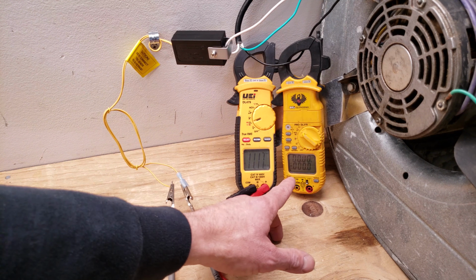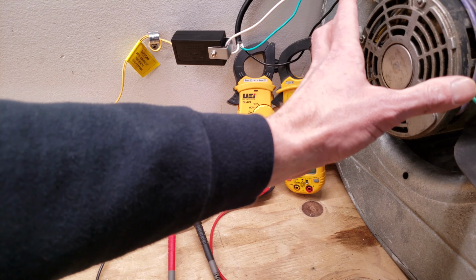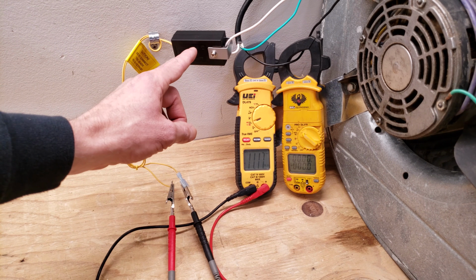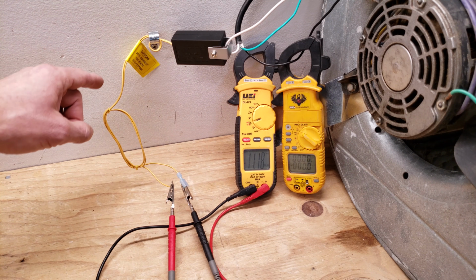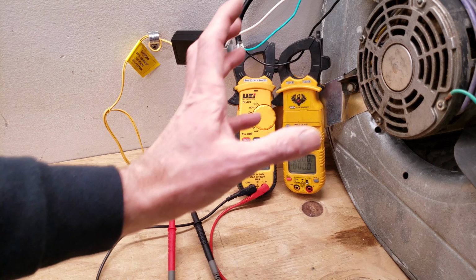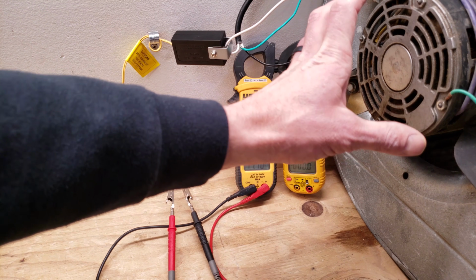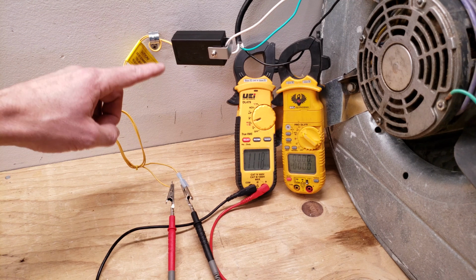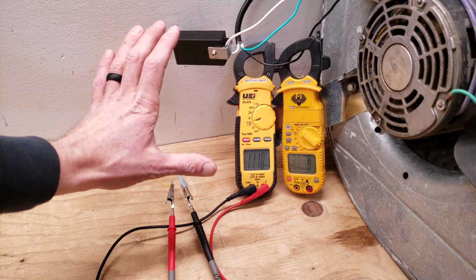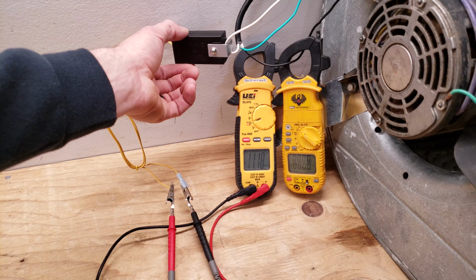But you need to make sure that you're drawing enough amperage on that blower motor for this current sensing relay to allow the 24 volts through. So on newer, higher efficiency blower motors, the amperage may not be high enough to allow this to send the 24 volts through. So that's something to keep in mind anytime you were to try to use this.